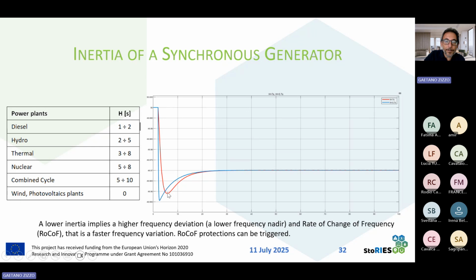The difference in frequency nadir is very important, because the frequency nadir can activate the minimum frequency protection relay, and can cause the detachment of the power plant from the system. So if the inertia of the system decreases, we have a higher probability that the minimum frequency protections, or the rate of change of frequency protections, are triggered, detaching the power plants. These are typical inertia values of power plants, and you can see in the tables that wind and photovoltaic plants have inertia that is equal to 0. So the increase of wind and photovoltaic plants is reducing the inertia of the systems.